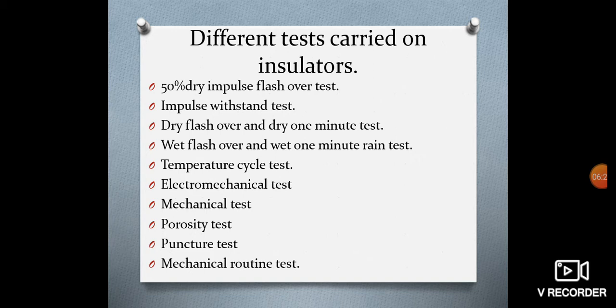Impulse withstand test. A standard impulse of 1/50 microsecond wave of specified value under dry conditions, with both positive and negative polarities, is applied. If 5 consecutive applications do not cause any flashover or puncture, the insulator is deemed to have passed the impulse withstand test. Dry withstand test. Power frequency voltage is applied to the insulator and the voltage is increased to a specified value and maintained for 1 minute. Voltage is increased gradually until flashover takes place. The insulator is flashed over at least 4 more times. The mean of at least 5 consecutive flashover voltages must not be less than that specified in the specification.